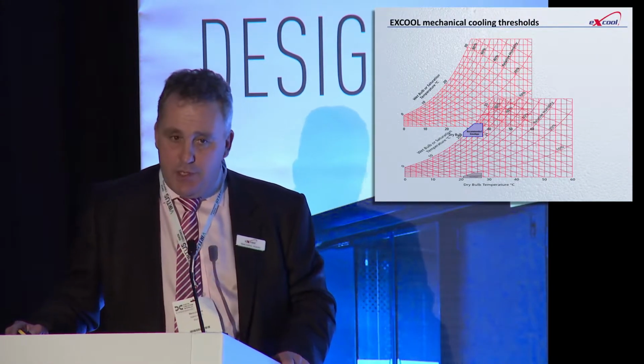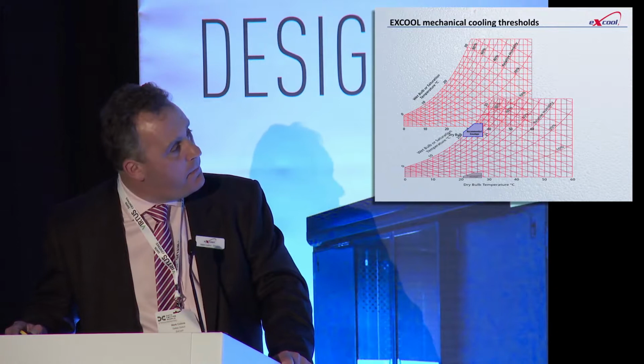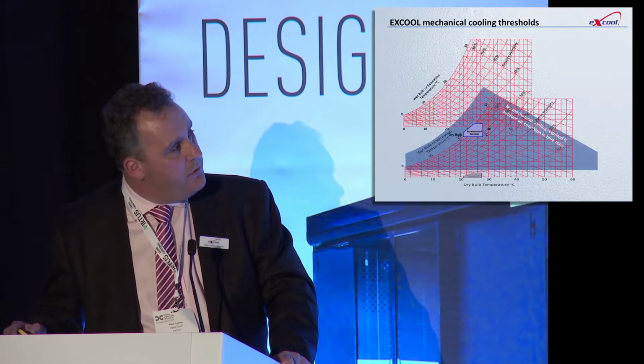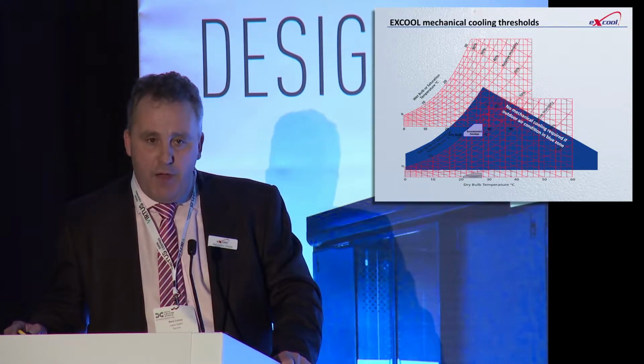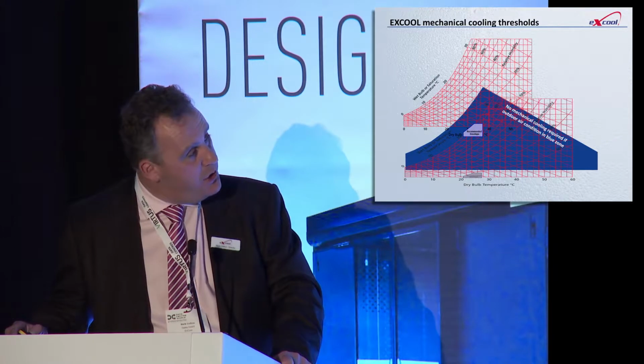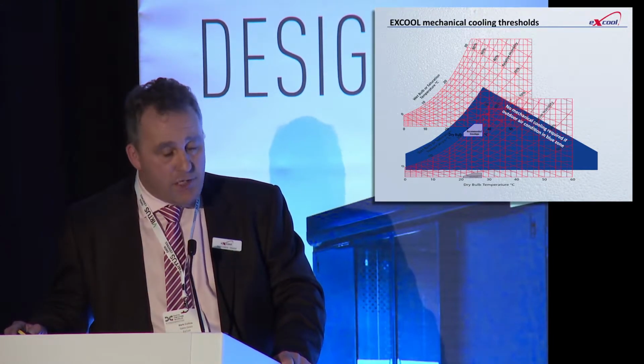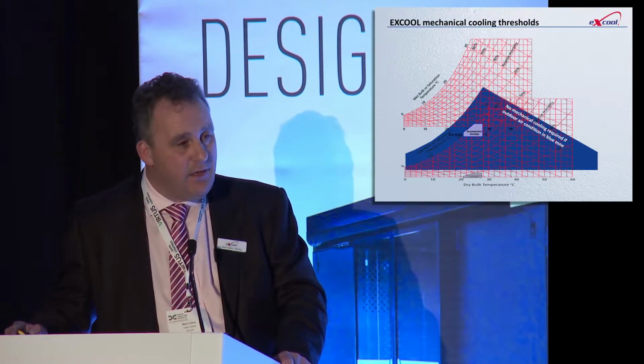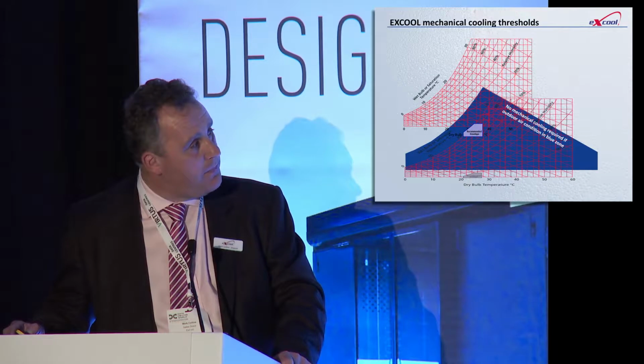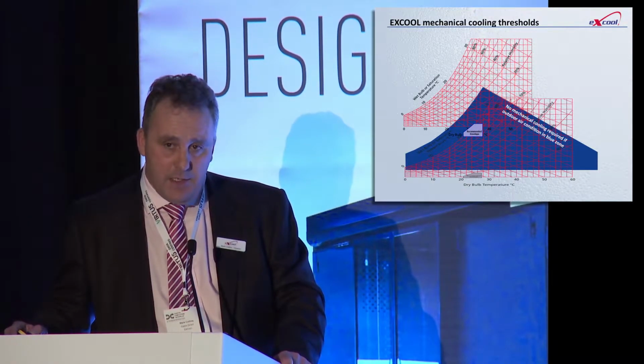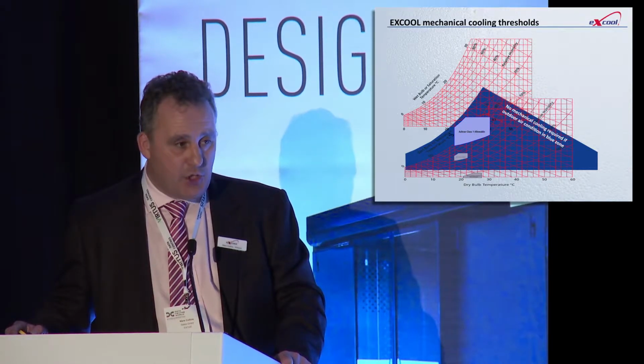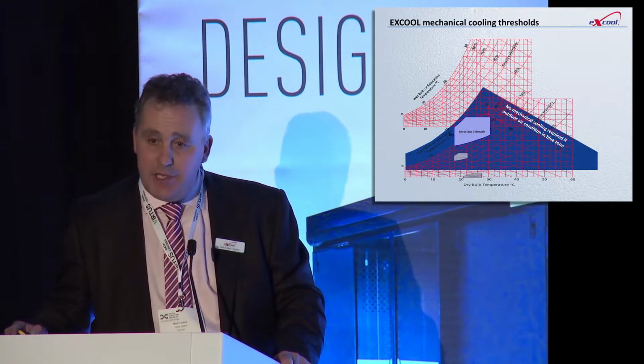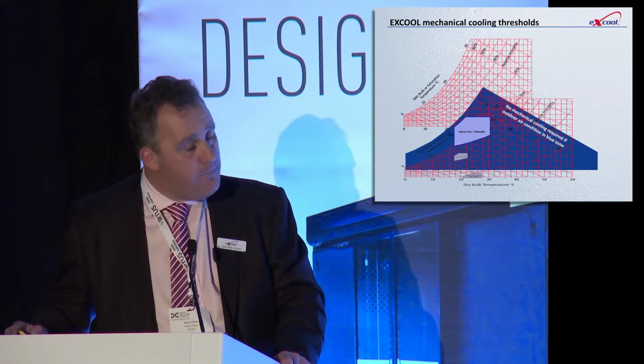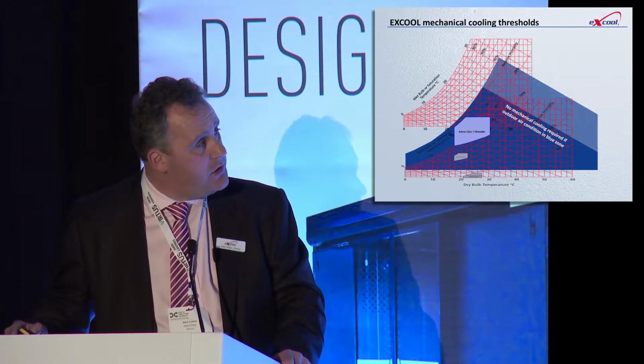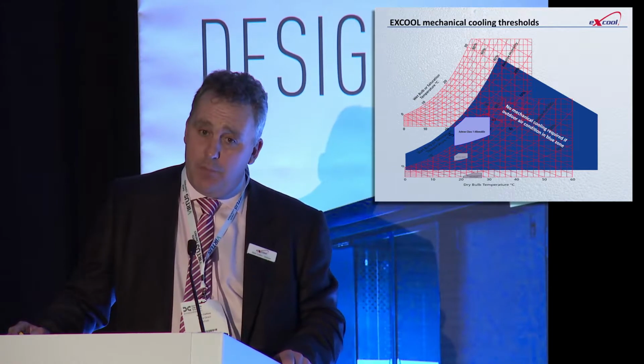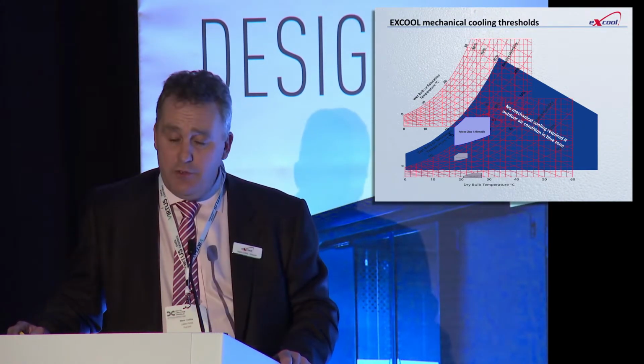Now, if we're trying to achieve supply conditions in line with the ASHRAE recommended envelope, providing our outdoor air condition remains in this blue zone, we do not need to provide mechanical cooling. So that's our outdoor air condition anywhere in that blue zone. You can see that we can be as hot as 50 degrees C externally, providing the outdoor air humidity is relatively low. And this is where it gets really interesting. If we have clients that are prepared to operate up to the ASHRAE allowable A1 class range, which allows air to be supplied at 32 degrees C for a few hours per year, then suddenly that zone increases to that point there.